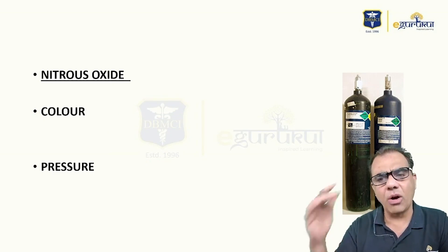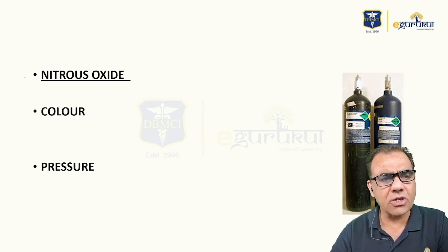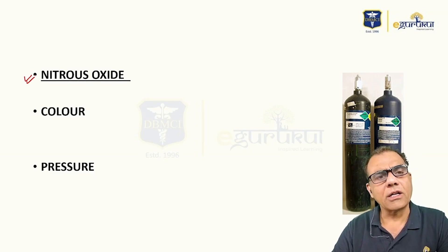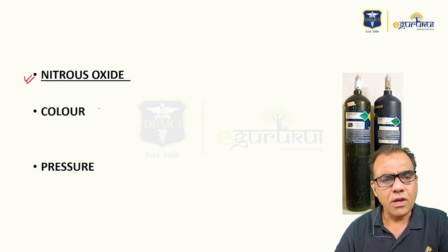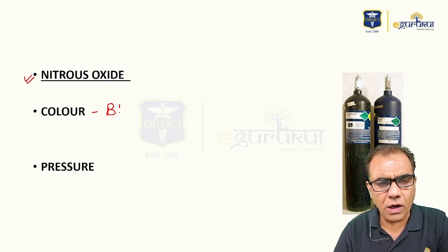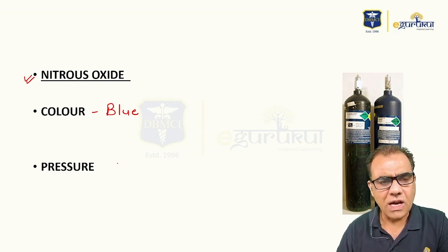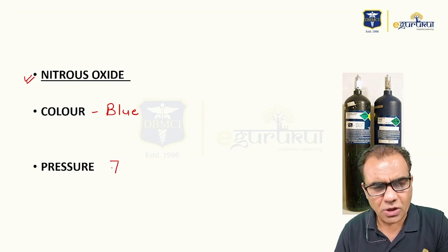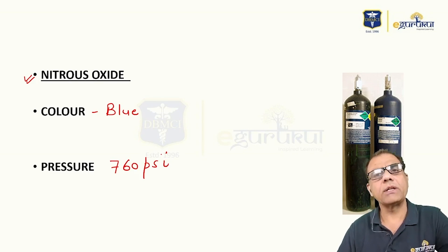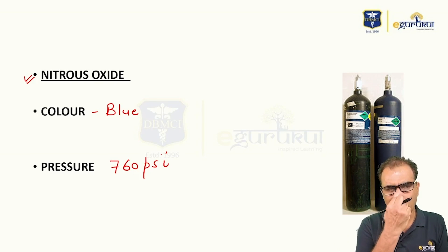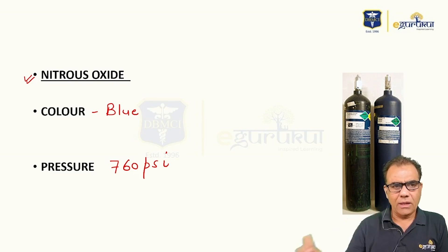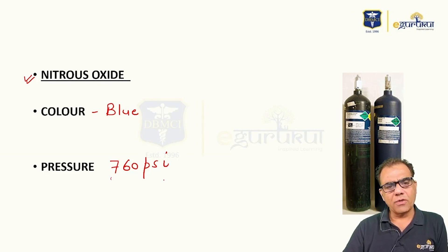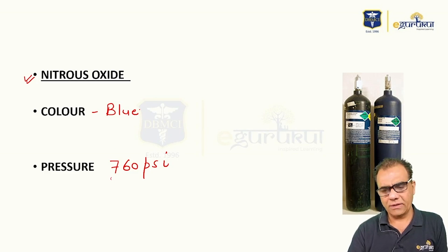The second cylinder in common use is nitrous oxide. Nitrous oxide is stored in blue color cylinders at a pressure of 760 pounds per square inch — blue color cylinders at a pressure of 760 psi.